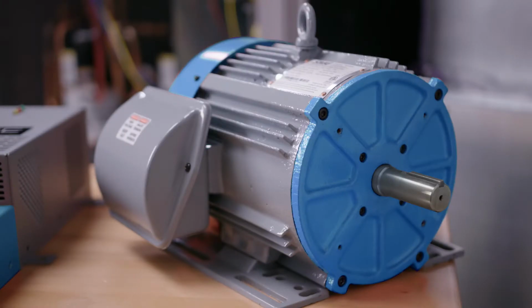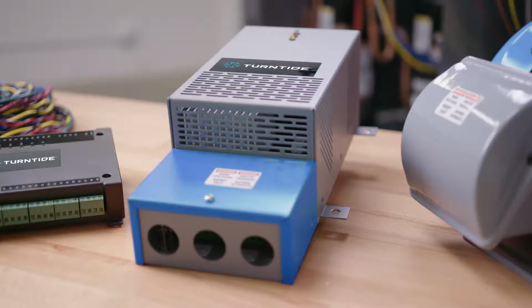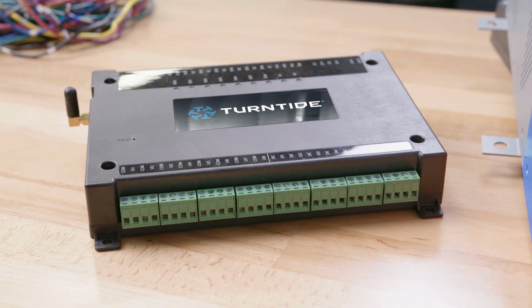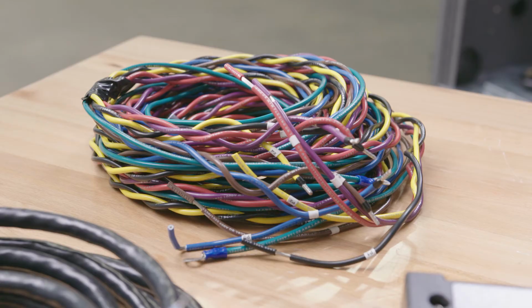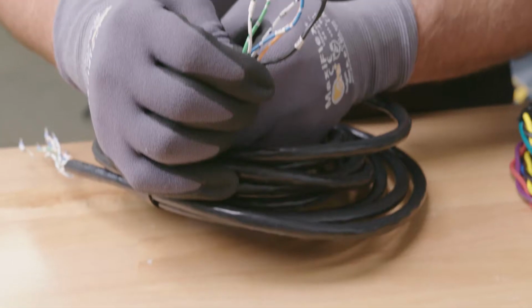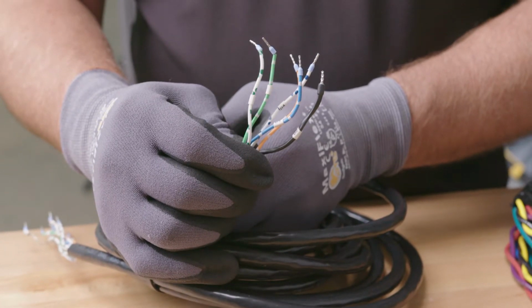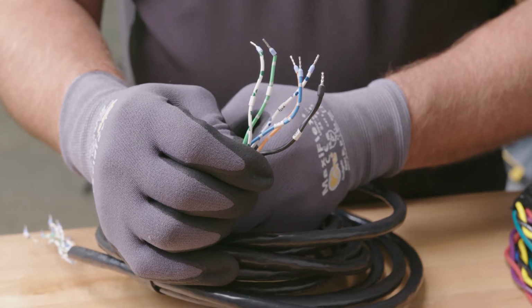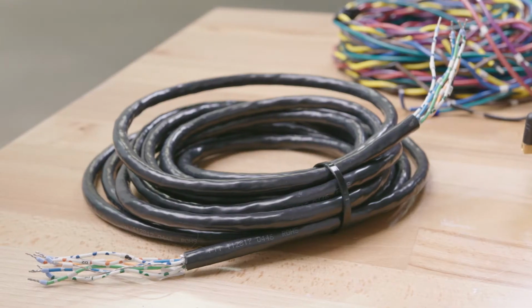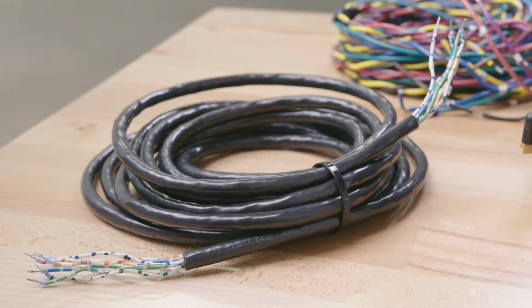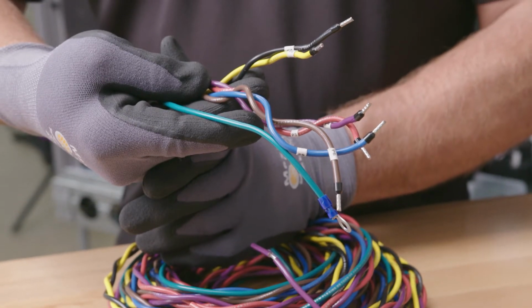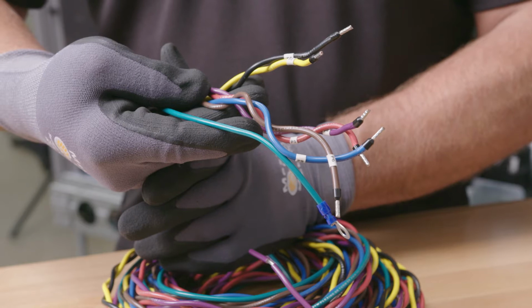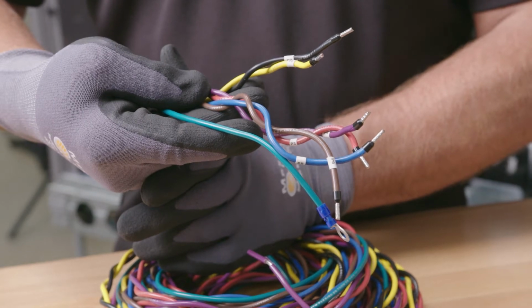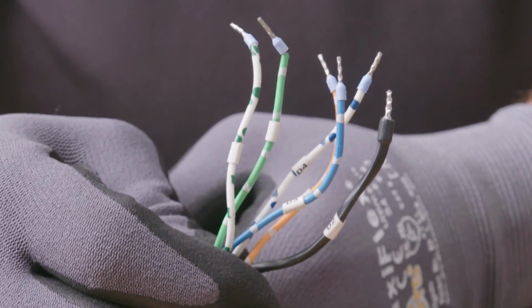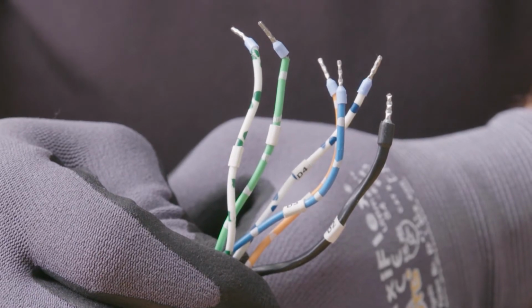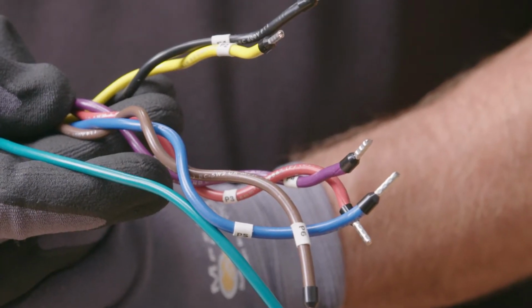The components in this installation include the smart motor, the motor controller, the supervisor, the 7-wire high-voltage motor control cable, and the 7-wire low-voltage motor data cable. These two cables are provided as they are required to provide connections between the smart motor and the motor controller. The number of wires is the key difference in wiring compared to traditional induction motors you've installed in the past.